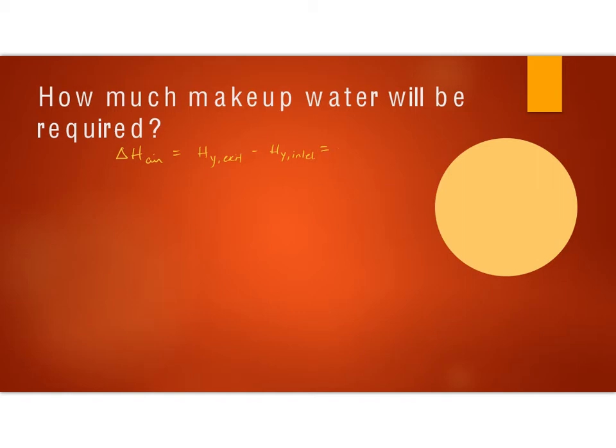And that came out to negative 86.08 kilojoules per kilogram of dry air. And multiplying by our flow rate, our delta H is 1,130 kilowatts, okay, and that's negative. This is of the air. Delta H for the water is simply the opposite of that.